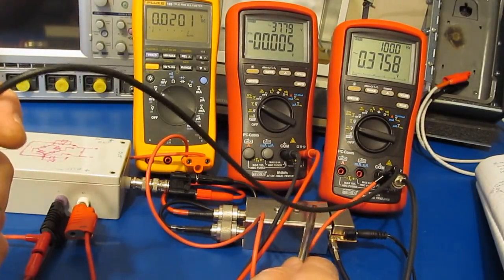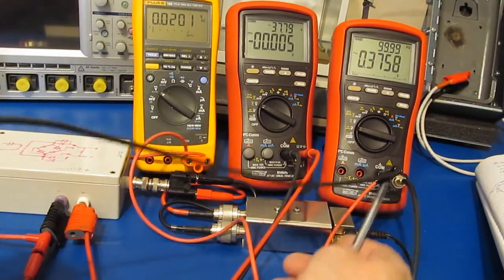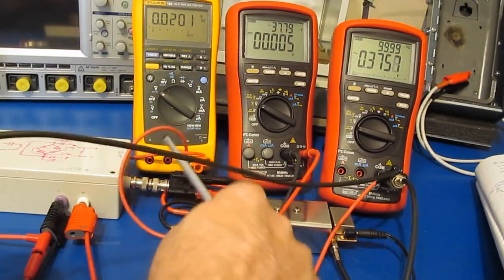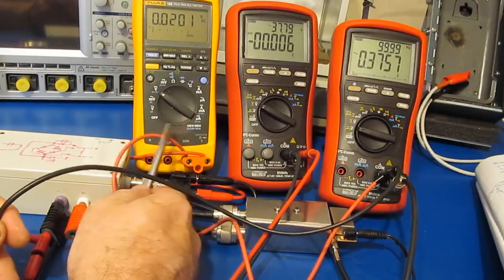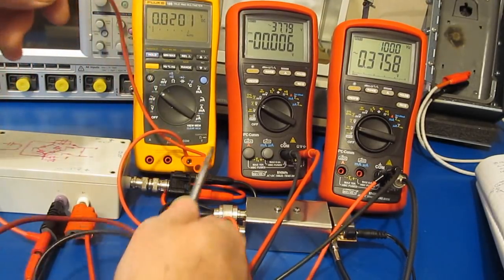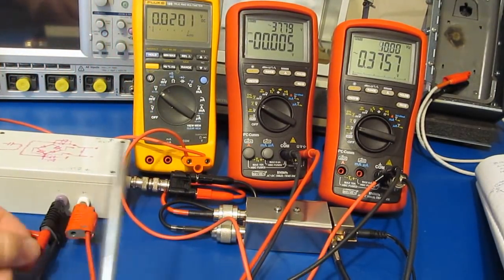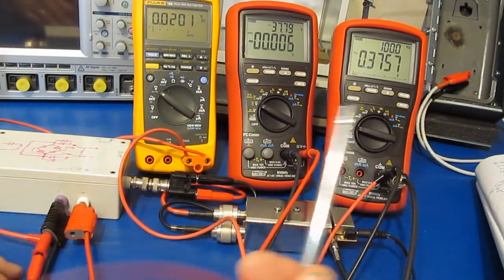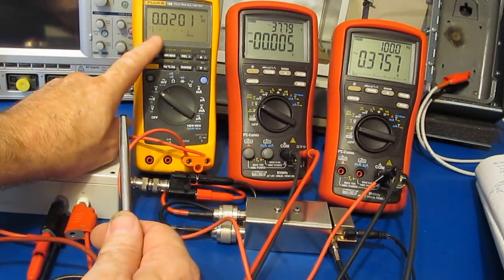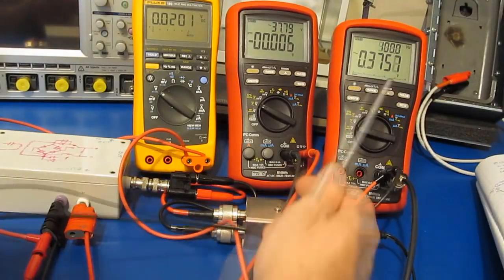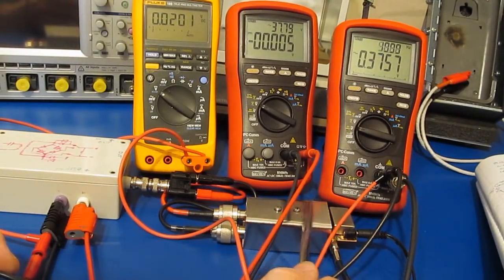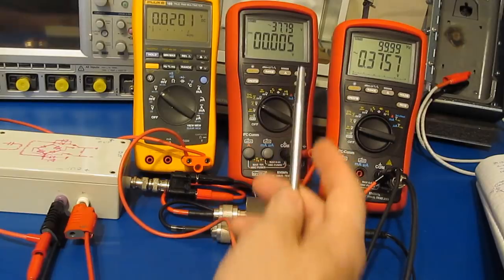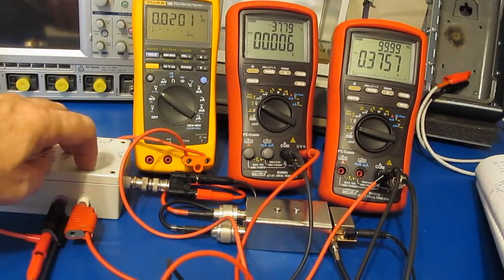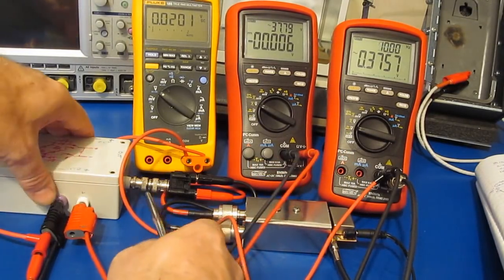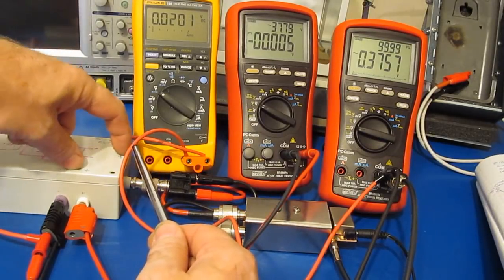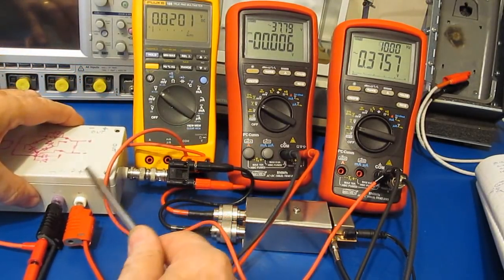Again, this meter is looking at the output from our probe. And you can see the common lead for this meter also goes back to the Fluke 189 on the left. The Fluke on the left, its positive input is going to our positive lead of the power supply. So this is just looking at the common mode voltage, essentially. And this meter, again, is just looking at the output of the probe. This meter in the center is looking at the output voltage of the transformer. Just to be clear, these two outputs are identical. These are hardwired inside of my box.